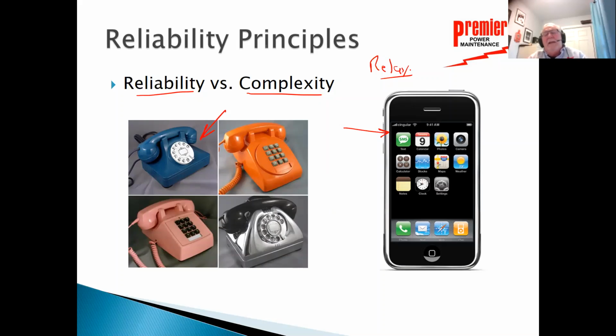I can remember back in the 70s when I was a relay engineer at Indianapolis Power and Light Company, when we were working with the electromechanical relays, and I could take that relay manual back to the motel room at night and read that manual, and it was 15 or 20 pages long. When you look at a relay manual today on one of those microprocessor-based relays, it's 300 pages long. It is complex. That relay can do pretty much anything that you could possibly want to do. Sounds great. But here's what I want to say. If you take that old electromechanical relay, we're still testing those things, some of them approaching 70 years old right now.